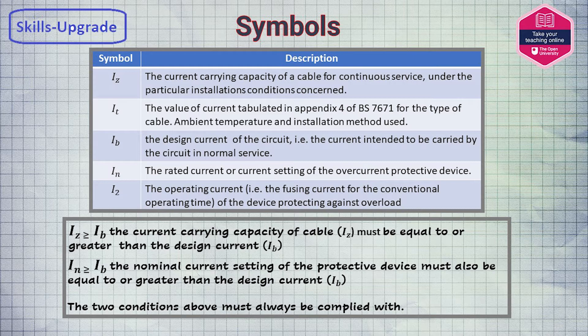IB is the design current of the circuit, i.e. the current intended to be carried by the circuit in normal service. IN is the rated current or current setting of the overcurrent protective device. And I2 is the operating current of the device protecting against overload.